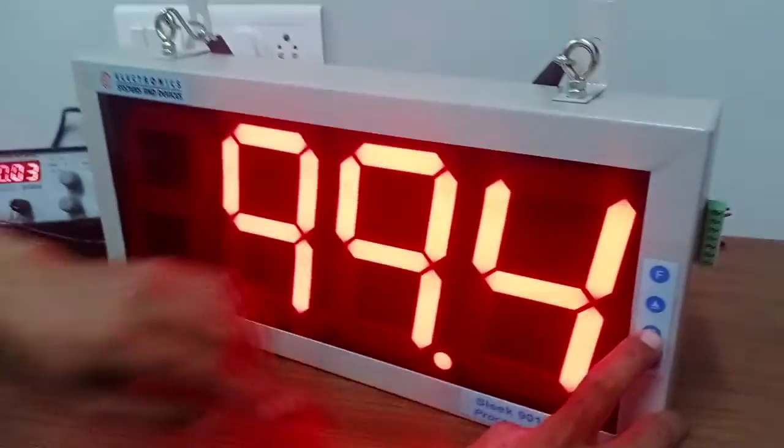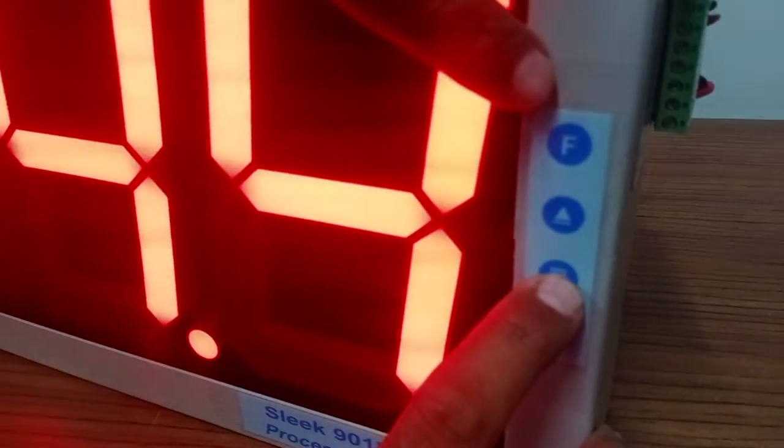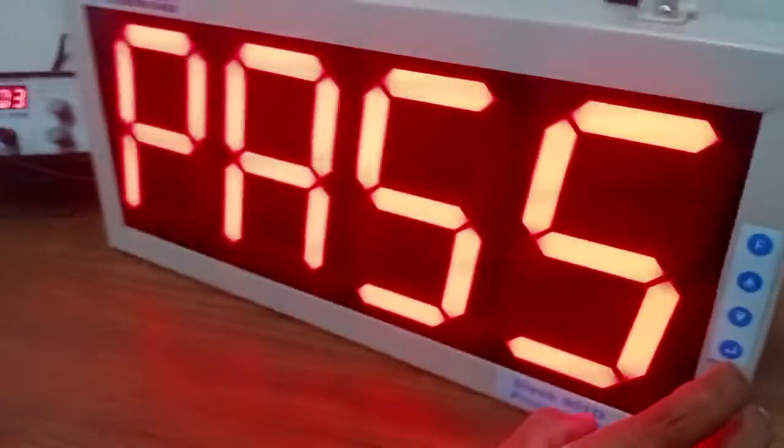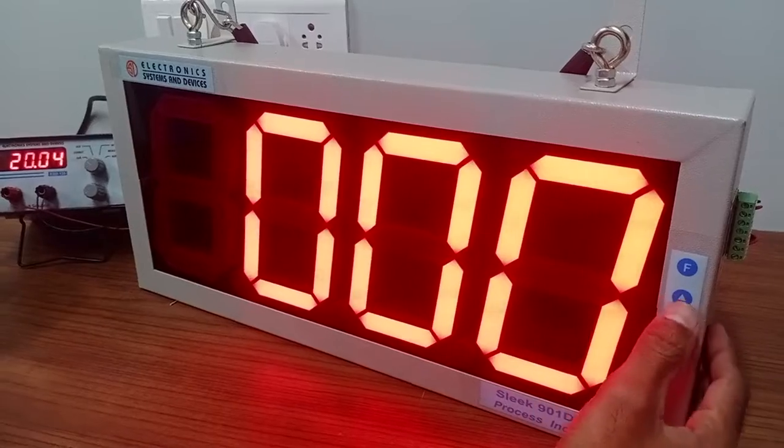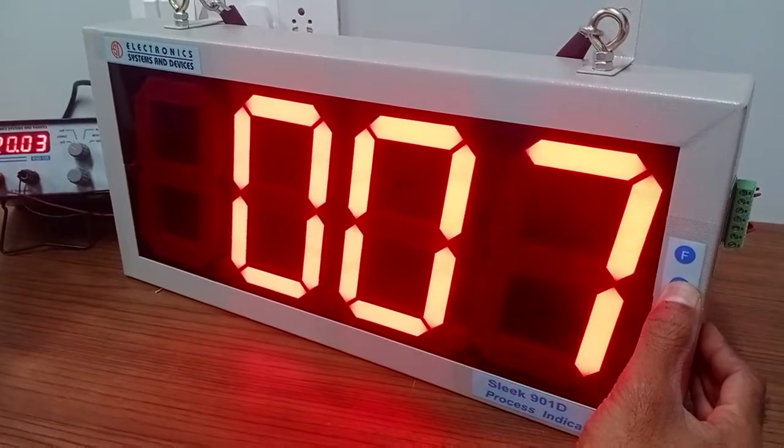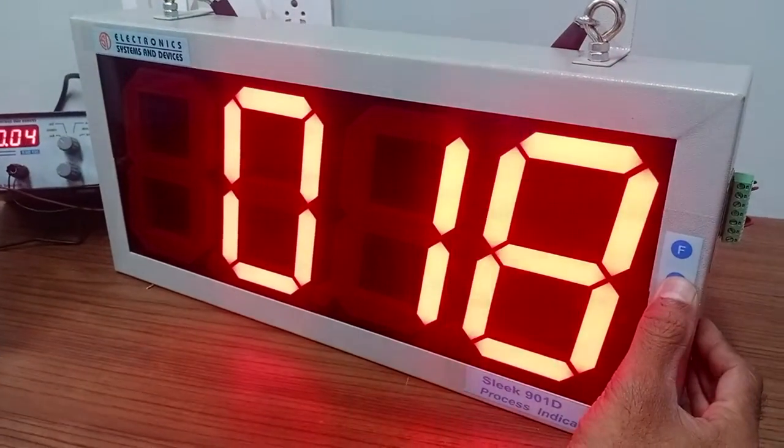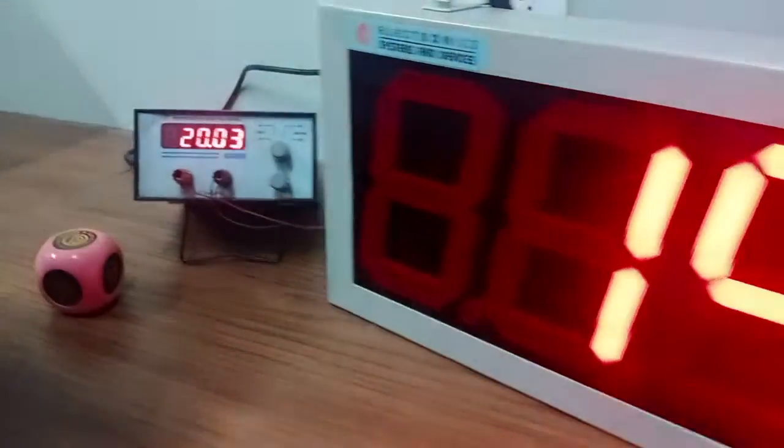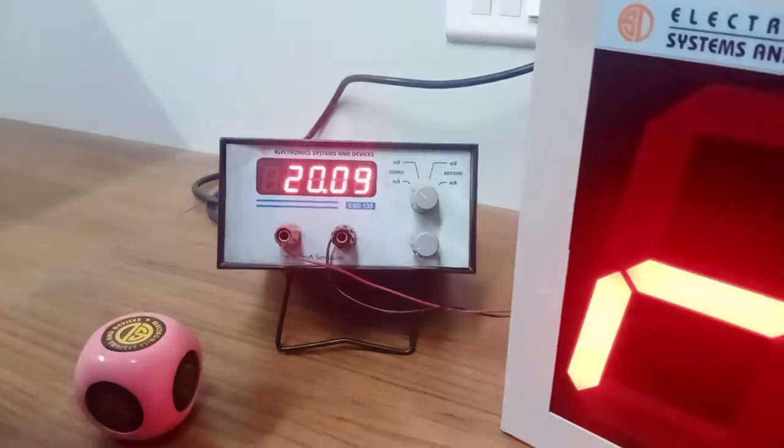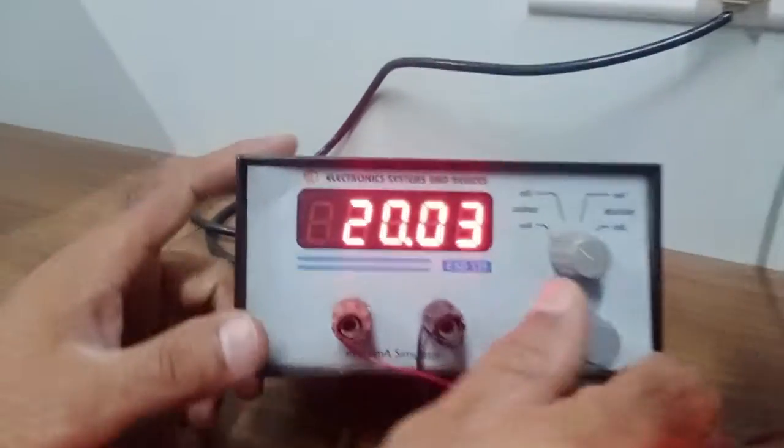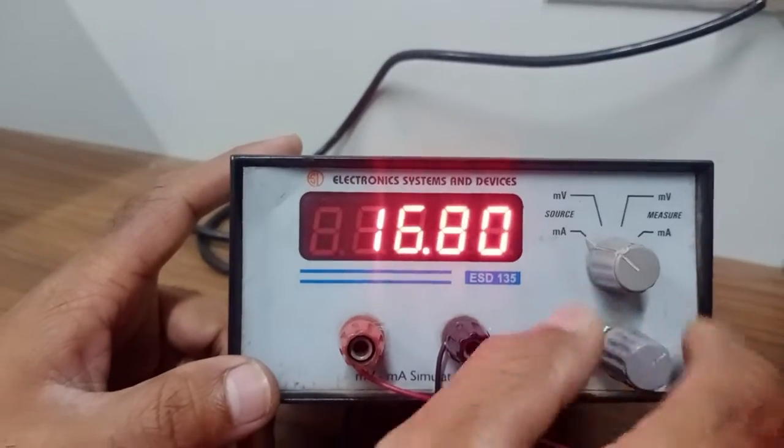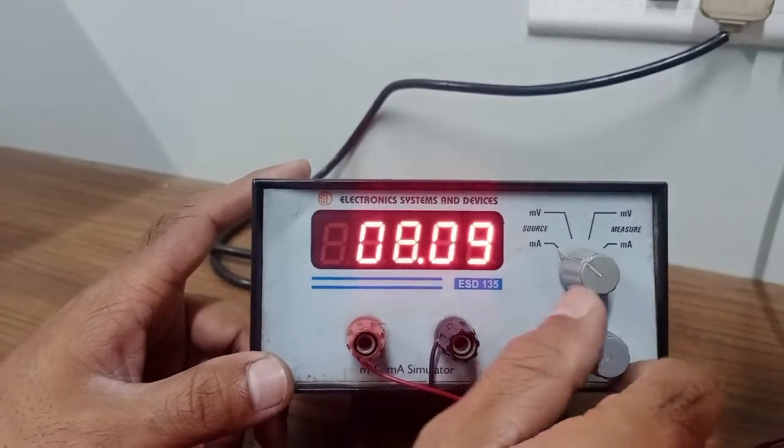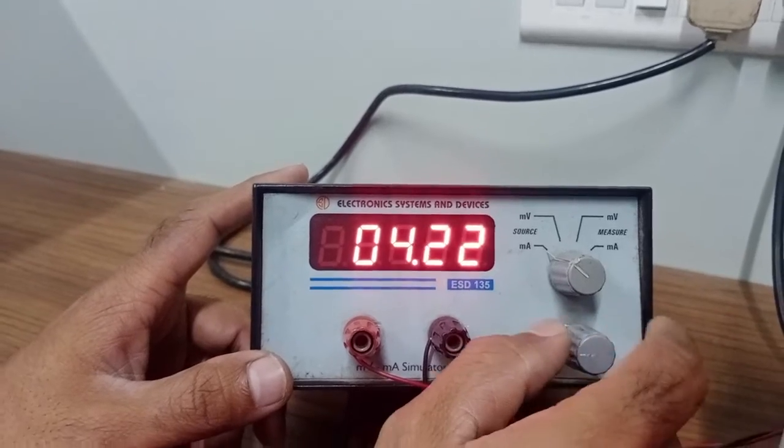Then we go to calibration mode. For calibration, you have to press the down arrow and the function key. It will ask for the password. The default password for calibration mode is 191. We are using Electronic Systems 135, which is a milliampere and millivolt source simulator to feed the input. We will give the 4 milliampere input now.